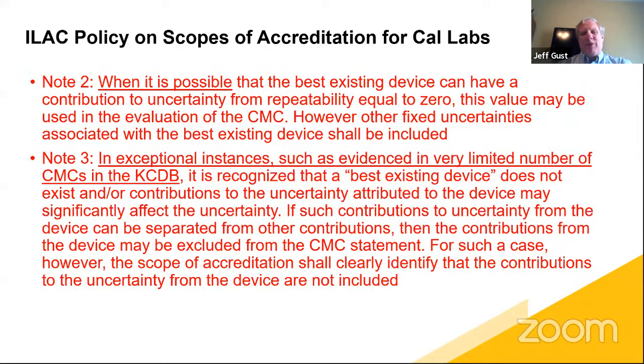But we did address one thing that was a problem with accreditation bodies and laboratories. And I'm sorry, but I'm on the side of laboratories here, folks. We would have a laboratory that would make a true CMC, and they would do an experiment on the repeatability and resolution of their best existing device, and they'd get a very small standard deviation, and that would cover their CMC. But then maybe they did hundreds of measurements, and on a better day, they got a smaller standard deviation, which turned out to, if you're automatically computing uncertainty on the fly, maybe calculate a smaller uncertainty than was on your scope of accreditation.